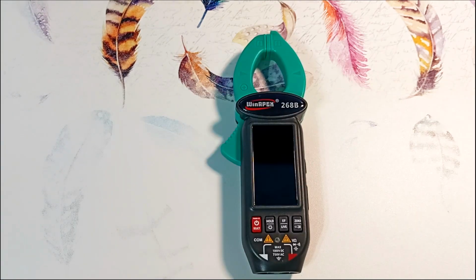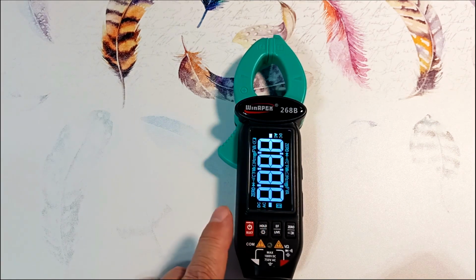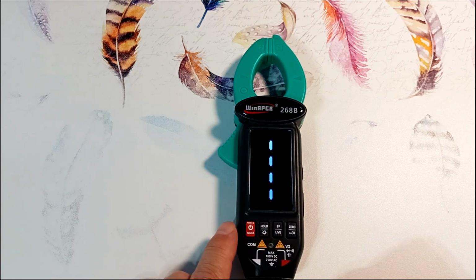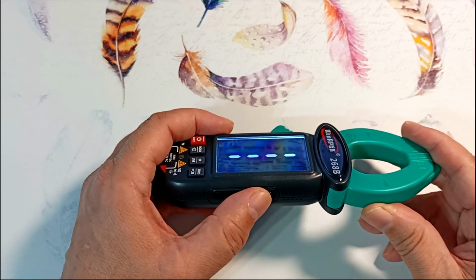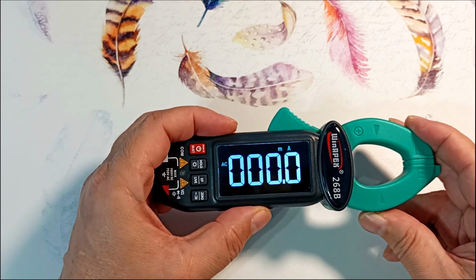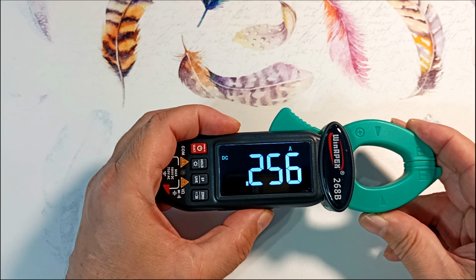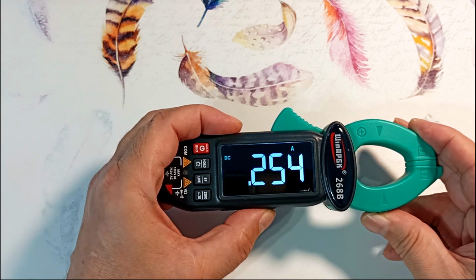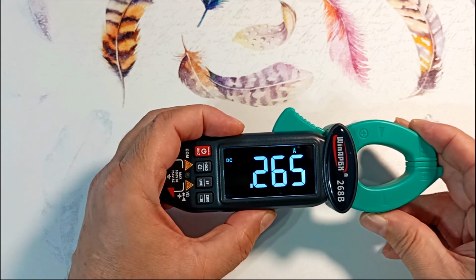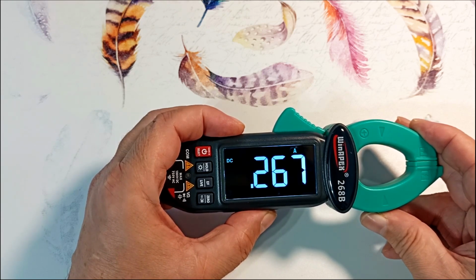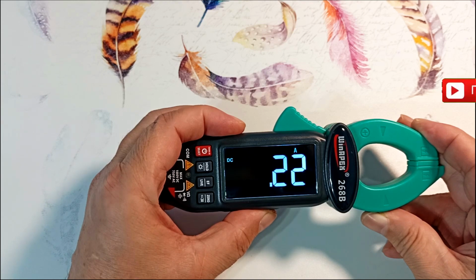How to use the device is intuitive. The red button is to turn on the power and go through parameters not related to current measurement. Turn it on. The device undergoes self-diagnosis and displays the following lines. This is the basic screen. Let's start with the most interesting function of the device, measuring direct and alternating current, as well as checking leakage currents. To measure current, you need to press the side button. We use it to select current measurement modes. To start, I selected the DC current measurement mode and the display shows DC. The device selects the measurement range itself. In this mode, you can select the most sensitive mode with 3 decimal places, and the less sensitive with 2 decimal places. Before measurements, the readings must be reset by pressing the 0 button.